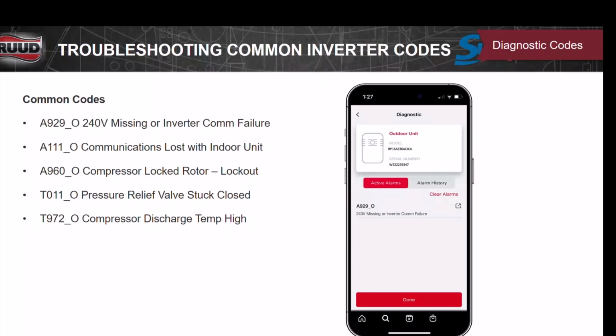And then pressure relief valve stuck closed. Of course, this is a new one. I haven't seen that one yet. Discharge compressor high, I've seen that. You'll see this whenever you have an undercharge, where our discharge line starts getting really hot, or our condenser coil's dirty, something like that. We see that a lot.